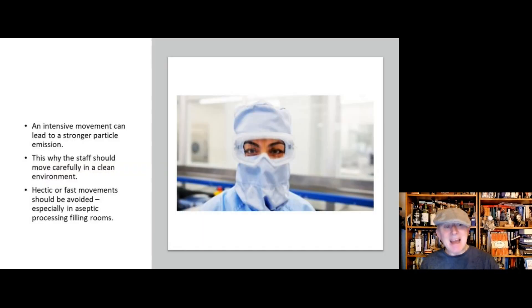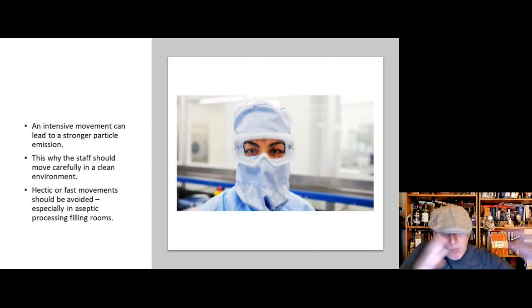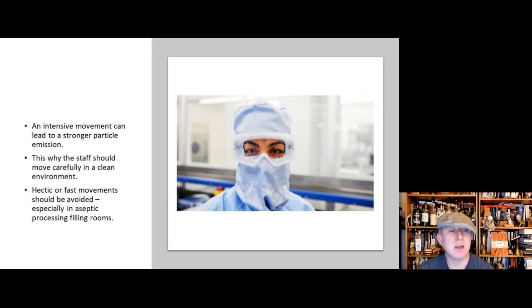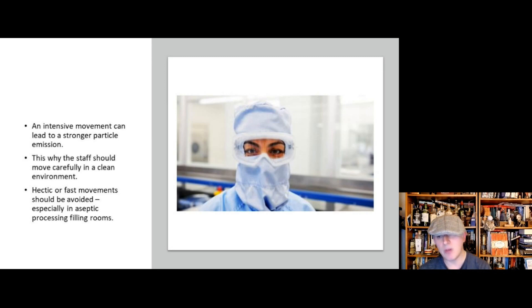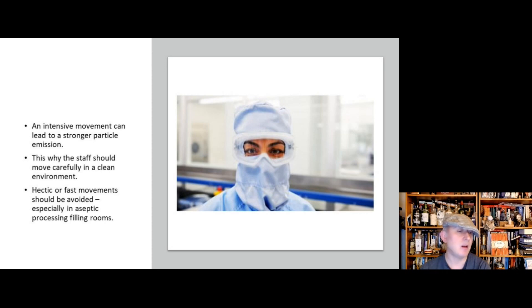Intensive movement and activity can lead to stronger particle emission. The faster and more frequent the movements, the greater the risk of particle deposition within the clean room. That's why people need to move slowly and consider whether their movements are necessary. Hectic and fast movements should be avoided at all times, especially within aseptic filling areas.